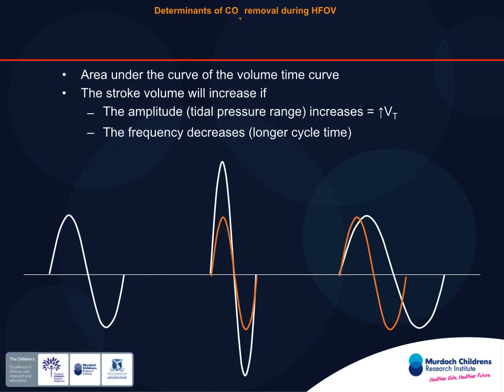So consequently, the things that will affect the area under the curve, let's see if my animation works this time, are making the curve bigger but keeping it the same width. That's changing our amplitude. That will obviously increase our tidal volume, but also making the curve wider or shorter but keeping the amplitude the same will influence our tidal volume. And this is really important because this is a difference from conventional ventilation, isn't it? Okay.